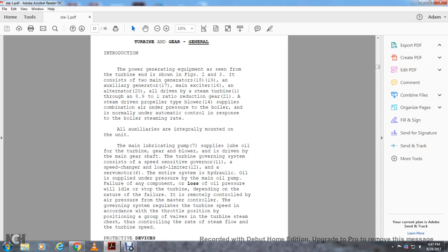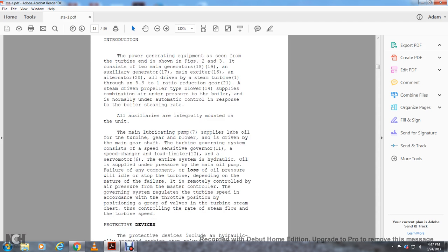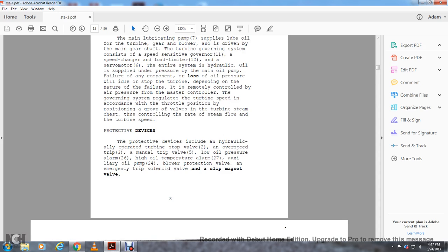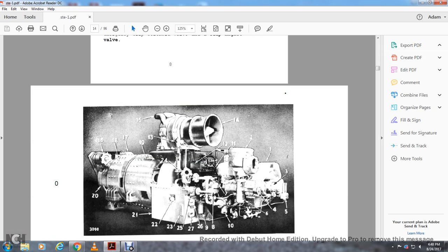Remotely controlled by air pressure from the master control, the governing system will regulate the turbine speed in accordance with the throttle position, by the position of the group of valves in the steam chest, controlling the rate of steam flow to the turbine. Protective devices. The protective devices include the hydraulically operated turbine stop valve 2 and the overspeed trip 3, the manual trip valve 5, and the low oil pressure alarm 26, high oil temperature alarm 27, auxiliary oil pump 24, blower protection valve, and an emergency trip solenoid valve and a slip magnet valve.